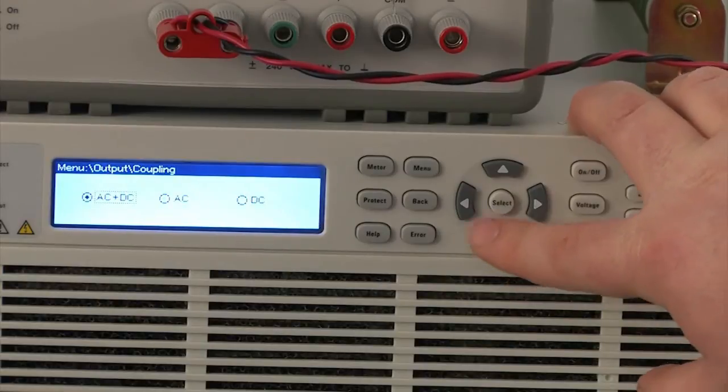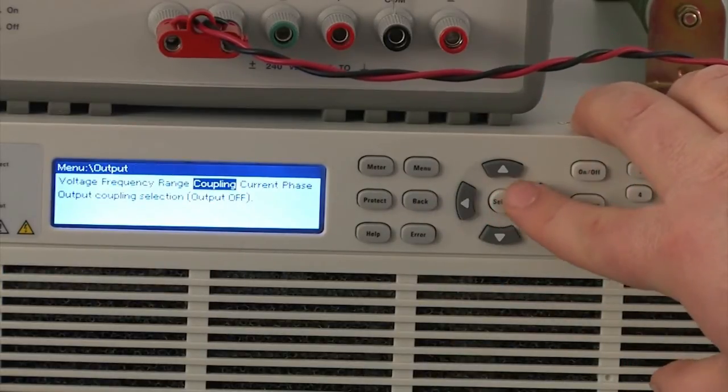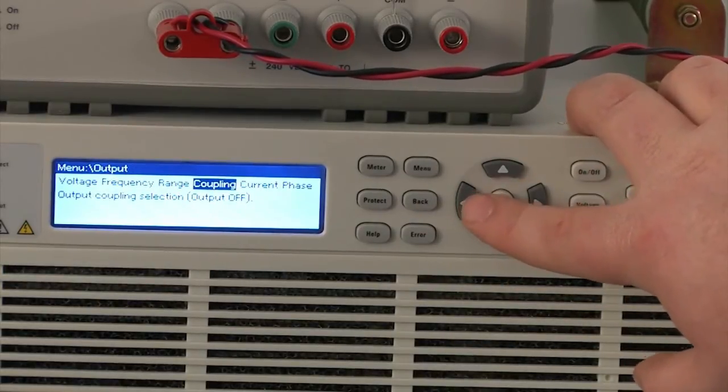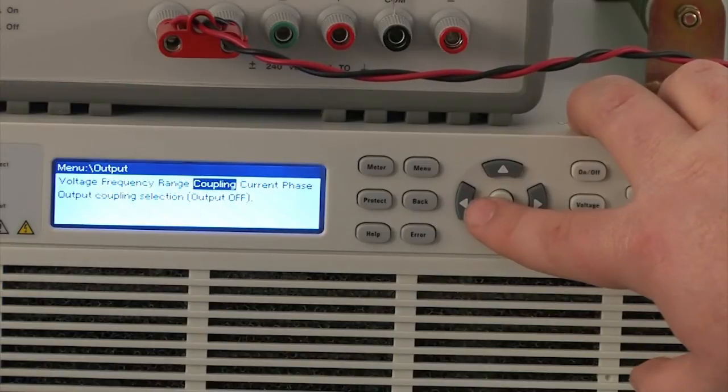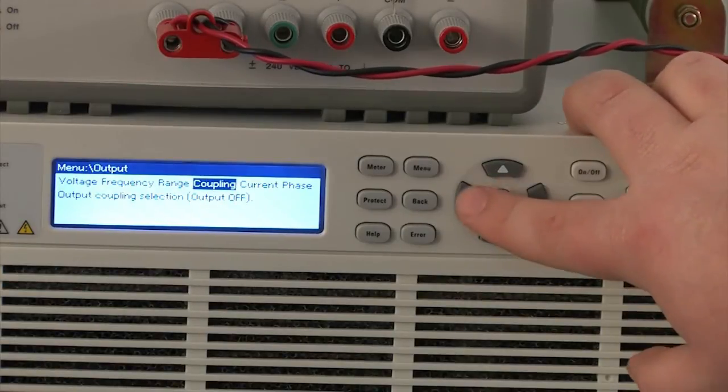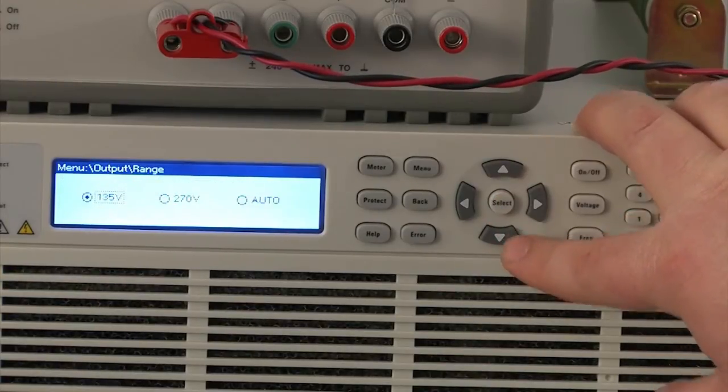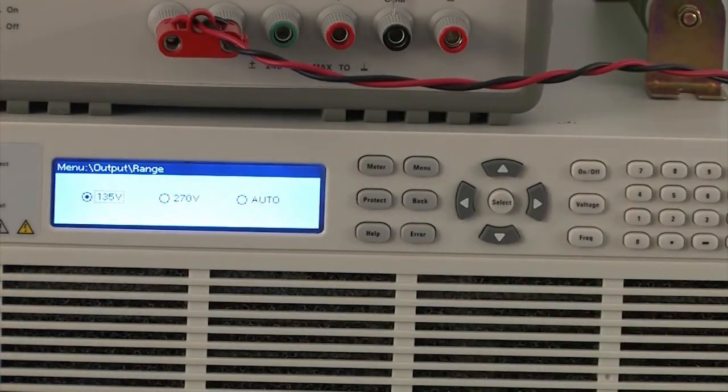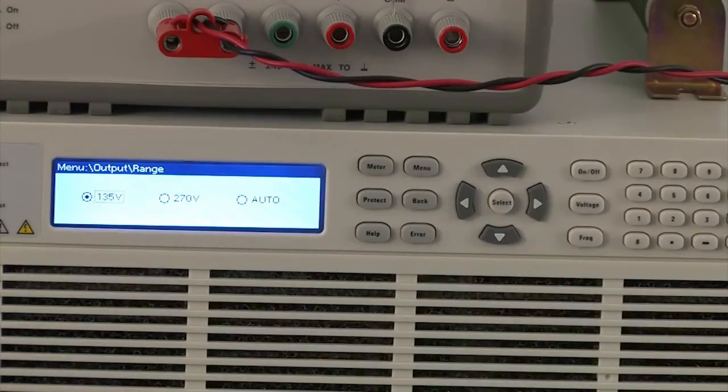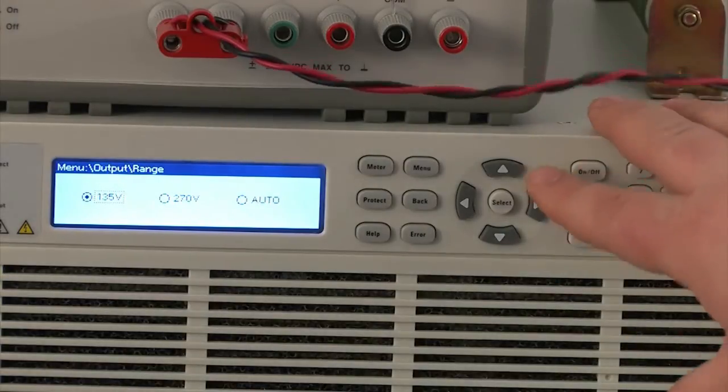So we'll choose AC and DC for now and hit back. And another feature that is pretty interesting is there's a range for output programming voltage. You can see that there's two different ranges. There's the 135 volt range and 270 volt range. You're going to want to use the 135 volt range for 120 volt testing, 100 volt testing, and 270 volts used for 240 volt testing and 230 volt testing.